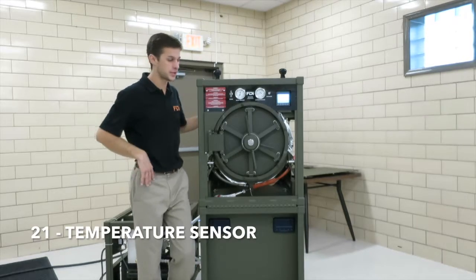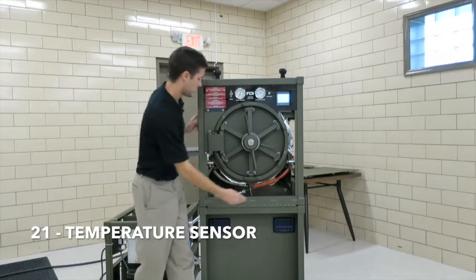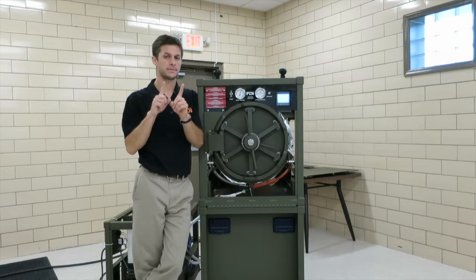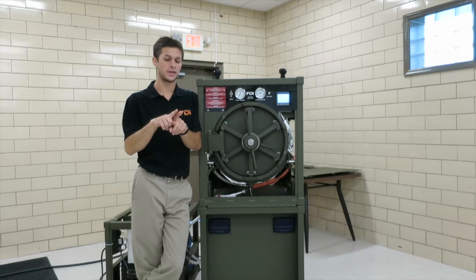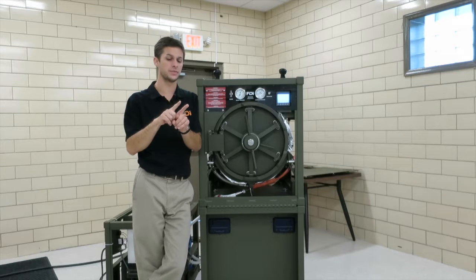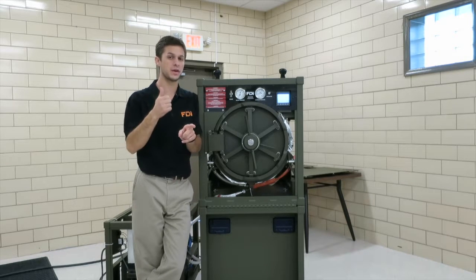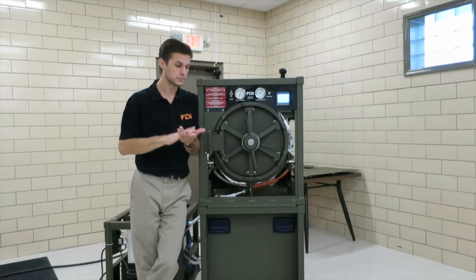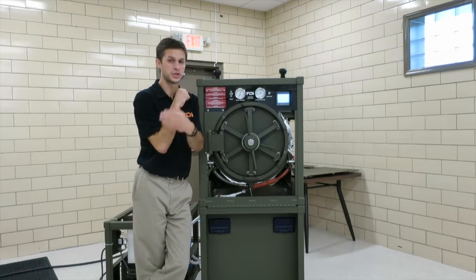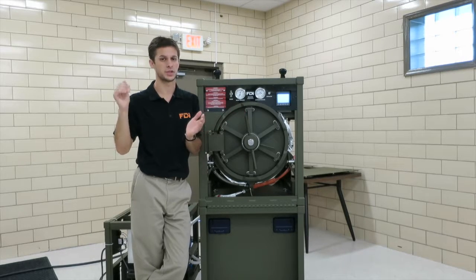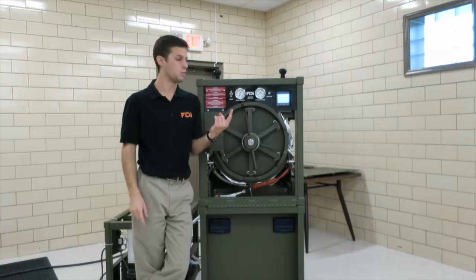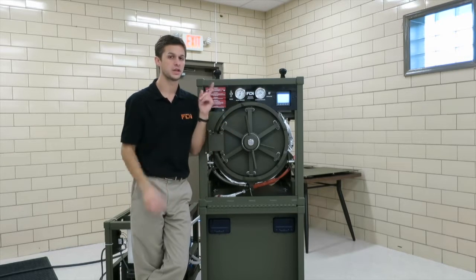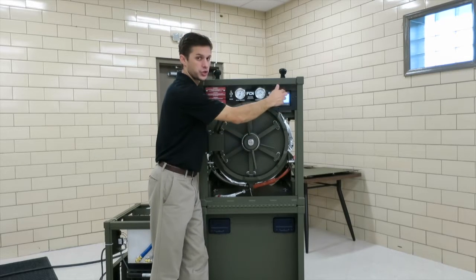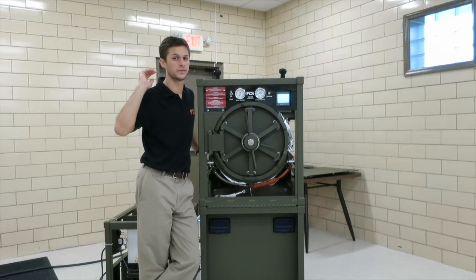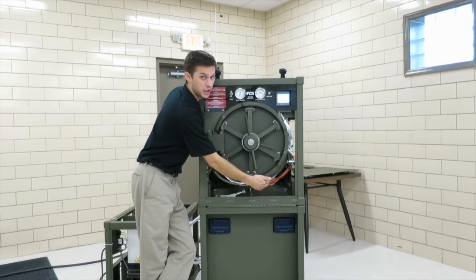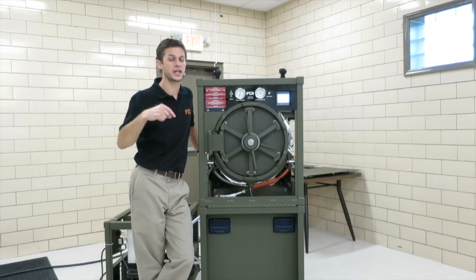So number 21 is temperature sensor. The temperature sensor down here has two elements in the end, two RTD elements. An RTD is a resistance temperature device. As the temperature goes up, the resistance grows, and the PLC knows that the temperature is going up. So it relates the resistance to temperature. But there's two because off of one, the sterilizer is controlling itself. When it's in exposure and it's hitting the set point of 273 degrees, it's controlling off of element 1 of the probe. Element 2 is checking up on 1.